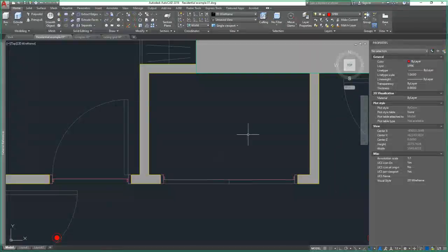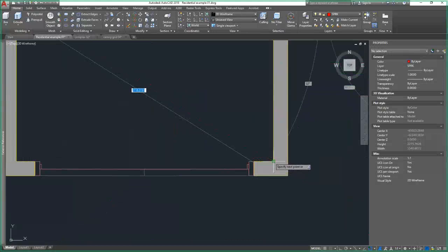So this here is some kind of storage cupboard. Do we need to protect this? Well, we should, because the limit, remember, for cupboards is 2 square meters. So large cupboards should be protected. Let's have a look at what size this is. It is 1.13 by 1.79. So yeah, it is just over 2 square meters. So we ought to sprinkler protect it.